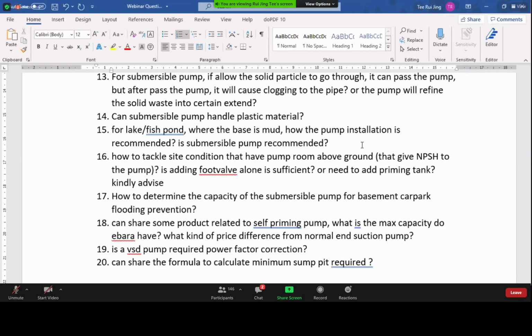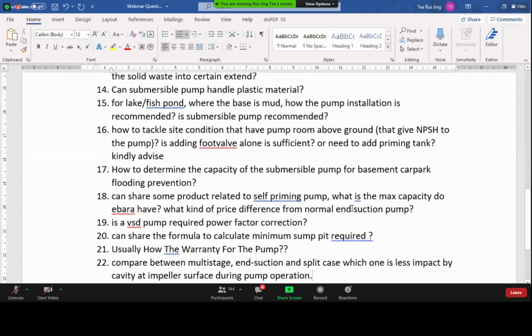So if you have such a situation, then it is very important to design a pit where the mud, as much as possible, is not inside the pit, because you must prevent the pump from pumping too much mud. So remember again that the pit design is very important. If you have a muddy base, let's say a river or something, then you have to have a channel, like an intake, where you can isolate the mud from the pump, or else you will have endless problems of the pump being clogged.